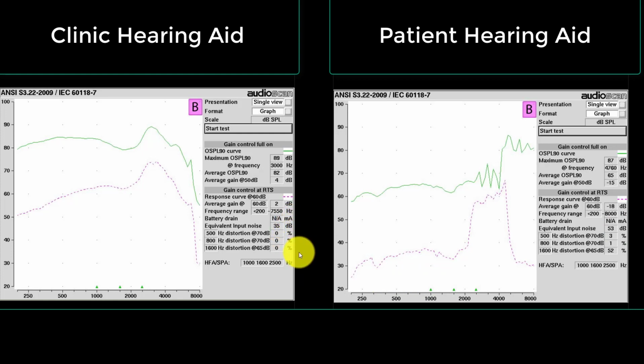The last thing that we look at is the amount of distortion coming from the hearing aid. The well-functioning hearing aid has 0 distortion as expected, but the patient's hearing aid has anywhere up to 52% distortion, which is basically destroying the sound quality. Based on these results, we know that this patient's hearing aid needs to be sent in for repair. There is nothing that we can do programming-wise to make any of that any better.